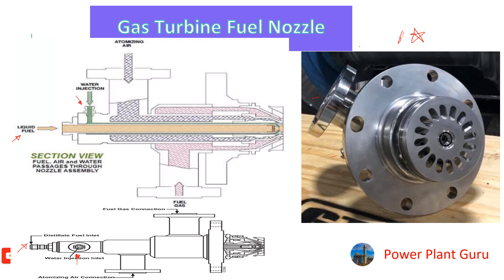You can see water travels just after the liquid fuel. There is a circular passage available in the fuel nozzle centerpiece, and around that, demineralized water flows. Here at the venturi, this water is mixing with your liquid fuel. The venturi is designed to create a low pressure so that water can be mixed with the liquid fuel.